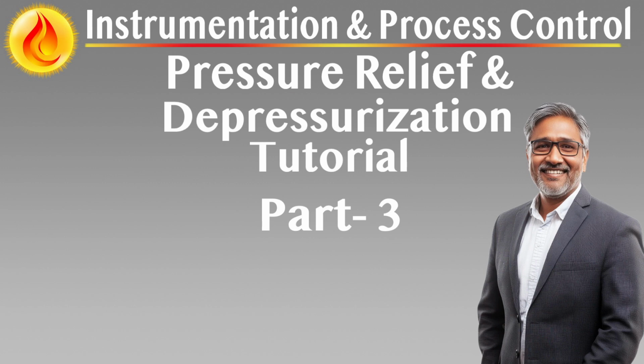Depressurization valves must be dedicated devices, separate from relief valves. They should be remotely operable, typically from the control room or remote safe location. In unattended or automated operations, the valves must be automatically actuated by triggers such as fire or gas detection. For critical systems, e.g. containing toxic or high-energy fluids, depressurization may also serve as a means to reduce release duration during leaks. Valve sizing objectives.